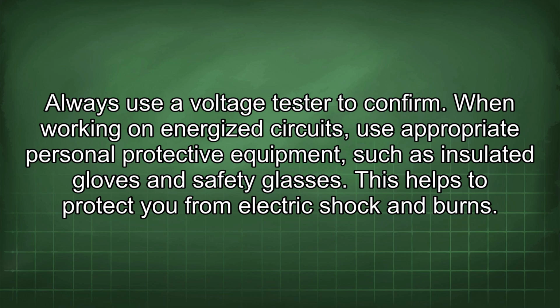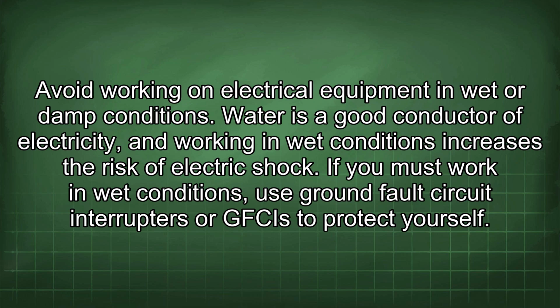When working on energized circuits, use appropriate personal protective equipment, such as insulated gloves and safety glasses. This helps to protect you from electric shock and burns. Avoid working on electrical equipment in wet or damp conditions. Water is a good conductor of electricity, and working in wet conditions increases the risk of electric shock. If you must work in wet conditions, use ground fault circuit interrupters or GFCIs to protect yourself.